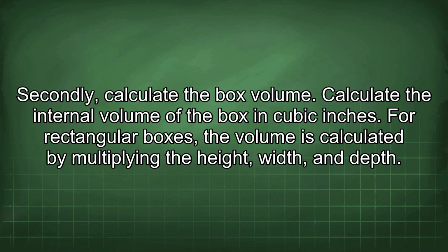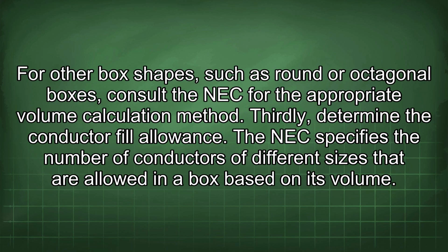Secondly, calculate the box volume. Calculate the internal volume of the box in cubic inches. For rectangular boxes, the volume is calculated by multiplying the height, width, and depth. For other box shapes, such as round or octagonal boxes, consult the NEC for the appropriate volume calculation method.